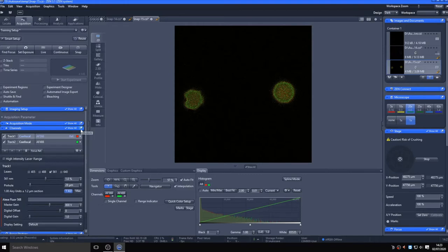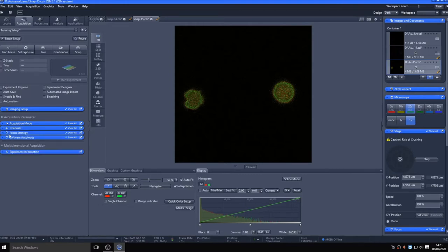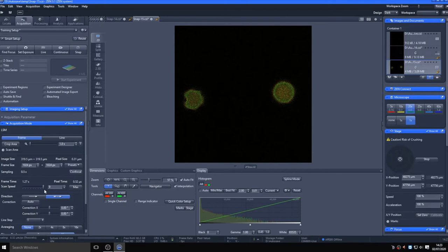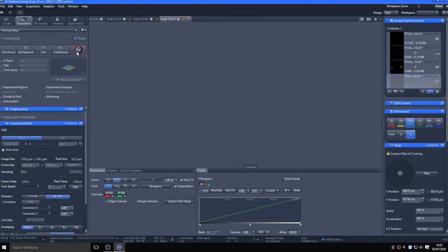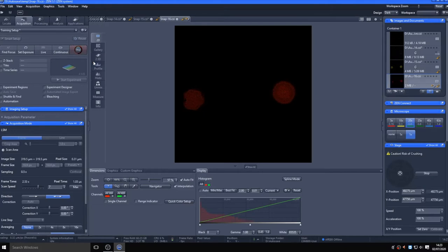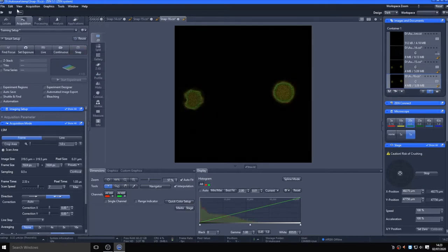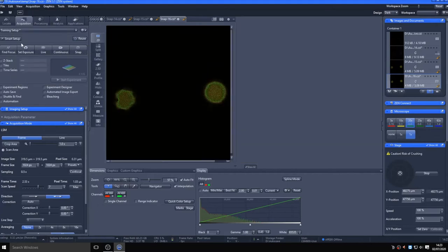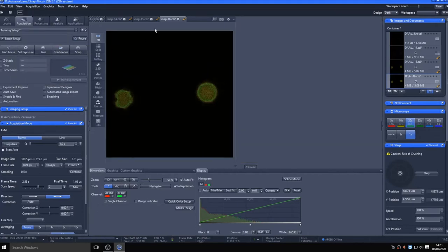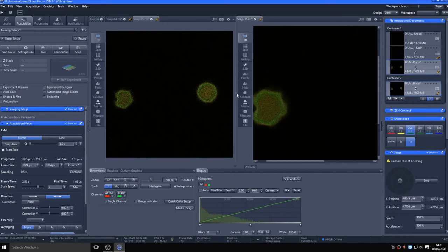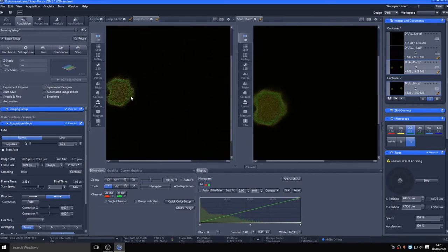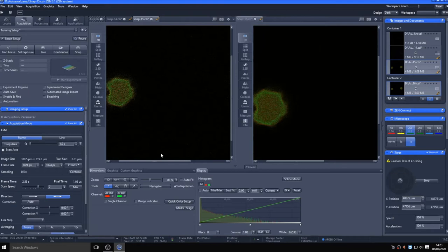To improve image quality, open the acquisition mode tab, and from here you can slow down the image scan speed. This increases pixel dwell time, allowing for longer integration time and produces a cleaner image with better signal-to-noise. Using the view tab to switch to two-container mode, comparing the two images, you can see the effect. A similar exposure is seen on the histogram, but a less grainy, better quality image is achieved at the sacrifice of longer imaging time.